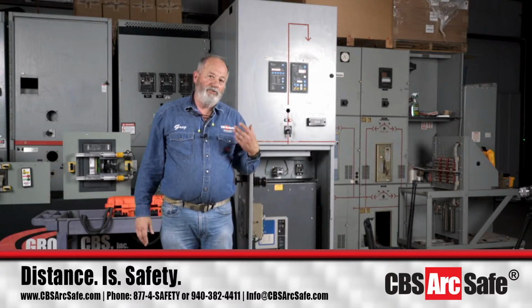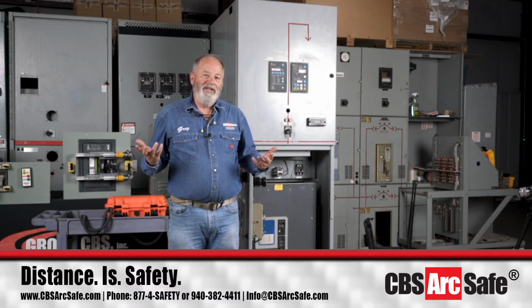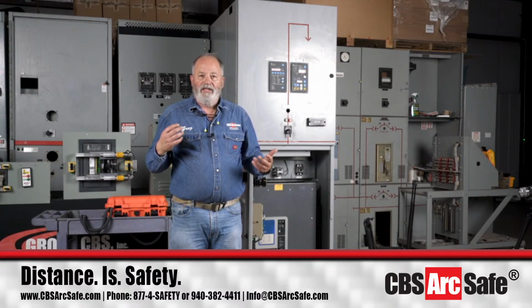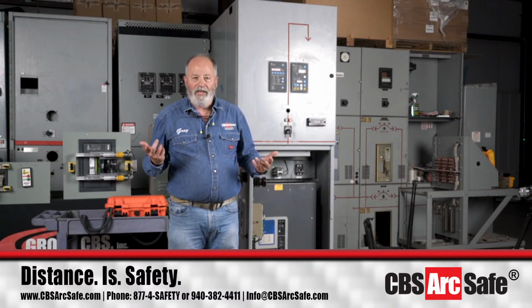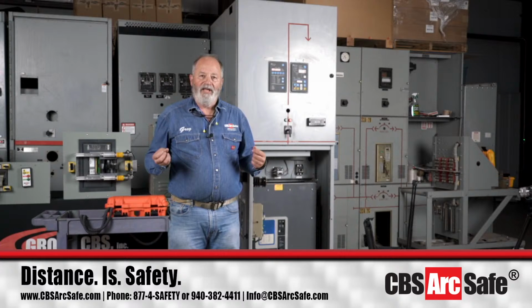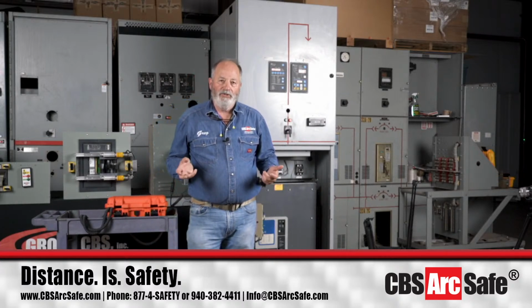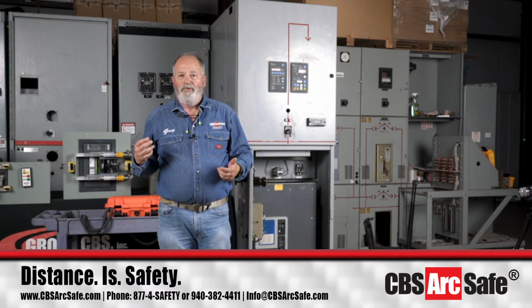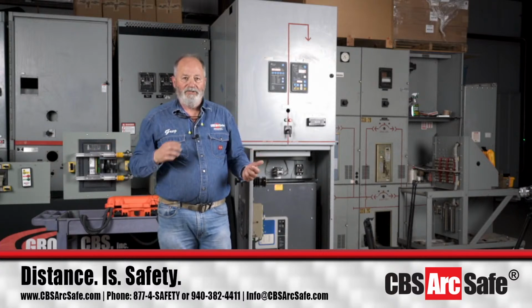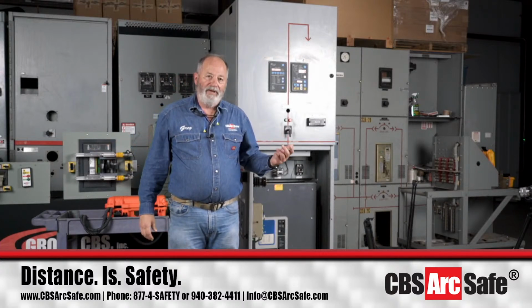And I've seen this also in a refinery, but the number of times you run into this stuff, it's less than 1% of the time. Okay, just understand, if you have something like this, you have a maintenance issue in the cubicle, and while the remote racking operation may be successful and everything else, you still have to address your maintenance issues.